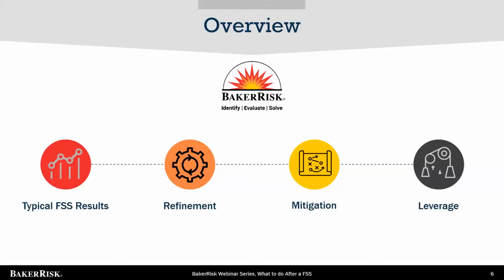The initial next step after performing a facility siting study is to compare results to company or industry tolerance criteria to determine whether the facility siting study results are considered broadly acceptable, tolerable if as low as reasonably practicable, or intolerable. Facility siting results that are considered broadly acceptable do not require further analysis or mitigation. Results that fall in the ALARP, or intolerable region, should initially be assessed using refined or more detailed analyses to reduce conservatism. However, results that still fall in the as low as reasonably practicable or intolerable region after refinement require mitigation or demonstration that results are ALARP, meaning that the cost of risk mitigation is grossly disproportionate with the level of risk reduction. Lastly, I will discuss how inputs and results from a consequence or risk-based facility siting study can be leveraged to perform additional technical safety studies at your facility.